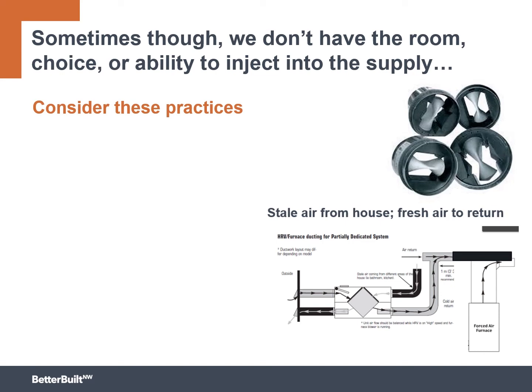If you look at the lower right-hand corner of the screen, you can see the ducting is going into the return side. So if you're going to do that, we want you to think of a couple of things. Don't install filter grills in the home, right? This is nice because filter grills, people tend to like them because homeowners can actually see the filter grill and they know to change out the filter. But part of the problem with that is as the filter gets dirtier, the more static pressure builds up in that return duct. And remember that the more negative static pressure in that return duct, the more it's sucking on that supply duct from the HRV. So that can be a challenge.